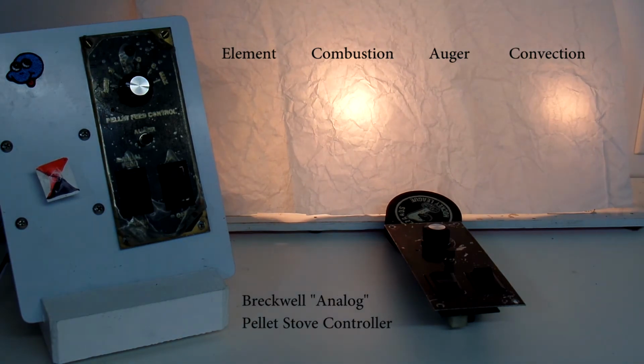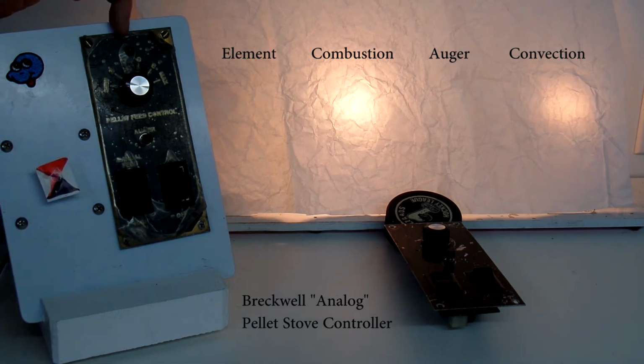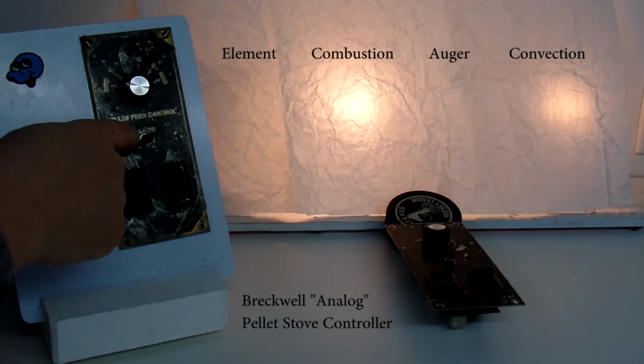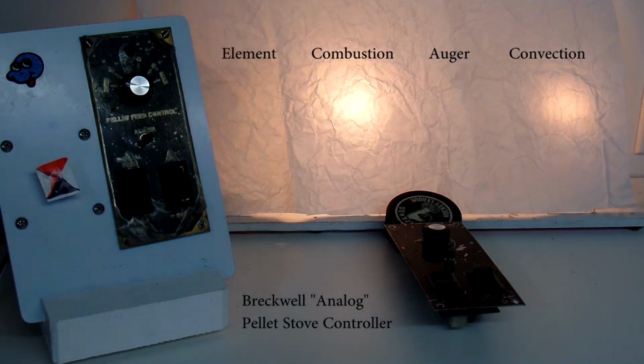The next test we'll do is go into automatic mode. To do that, we press on the auger button, and that will cause a green light to come on at the top and a timer to start within the controller. I will say that on this controller, it has the ability to also drive an igniter module. So when we press on the auger button, the top green indicator will come on, but when I release, we'll see the light bulb for the igniter come on as well.